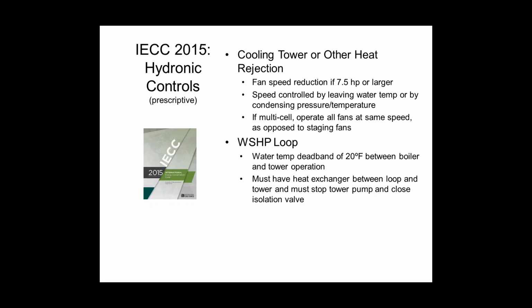If you have a water source heat pump loop type project, like we have many of in the city of Chicago, similar to the two-pipe changeover systems, we have lots of rules on the temperatures and so forth. We're required to have a water temperature deadband of 20 degrees between the boiler and tower operation. So I can heat the loop up, let's say for argument, I can heat the loop up to 60 degrees with the boiler. I can cool the loop down to 80 degrees with the cooling tower. And between 60 and 80 degree water temperature, I am not allowed to run the boiler or the cooling tower. Now, I just picked 60 and 80 in my head. You could have picked 55 and 75. You could have picked 65 and 85. But there's some 20 degree temperature of water that I'm not going to be allowed to run the boiler or the tower.